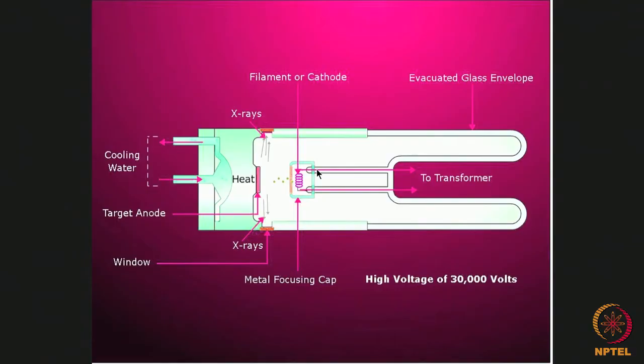The more modern x-ray tube nowadays, its cross section looks similar to this figure. As you can see here, we have got a filament, maybe a tungsten filament which acts as a cathode, and then you have a target which is a metallic target, this is the anode. As I already described, a small current, about 3 ampere current is passed to the filament, as a result of which the filament gets heated up and there is a thermionic emission of electrons. If a high potential difference is kept between the target and this filament, the negatively charged electrons will strike against the target at a very high speed and from the point of impact, x radiation will be produced and those x radiation will be taken out through some windows.